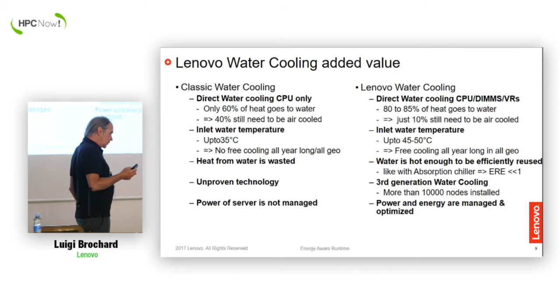One of the things people maybe don't know is that with a direct water cooling system, even with water at 35 or 40, you decrease the processor temperature and you decrease the consumption of the system. Because, in fact, the processor will be at a cooler temperature. Here is a comparison of an air-cooled system with a direct water-cooled system, where you see the temperature of the processor here and there, and you see there is a wide gap: 80 degrees for the air-cooled processor and 40 degrees with water. And therefore, you can benefit from it, either by reducing the power or by improving the performance.